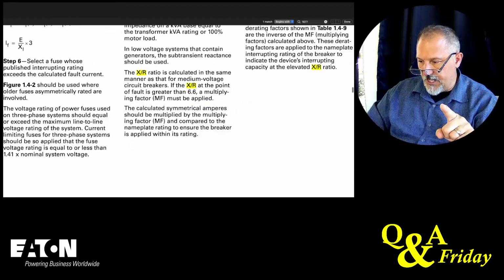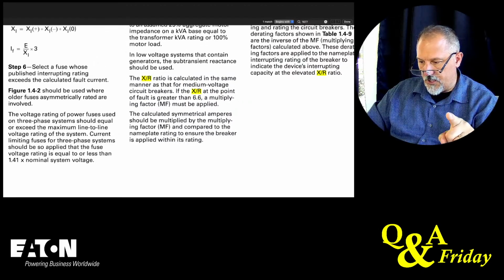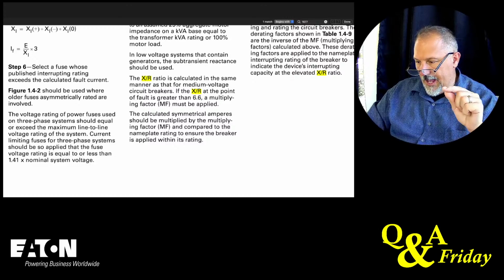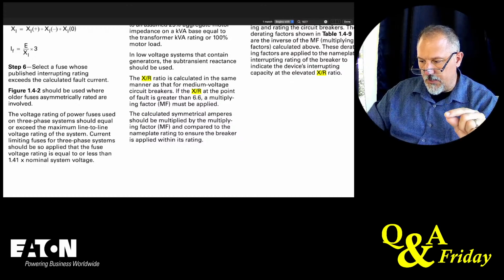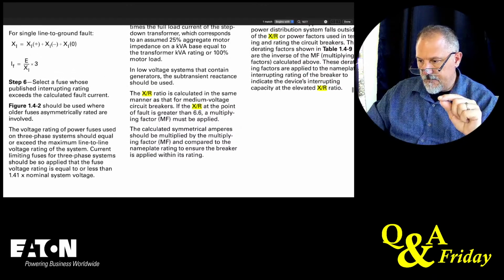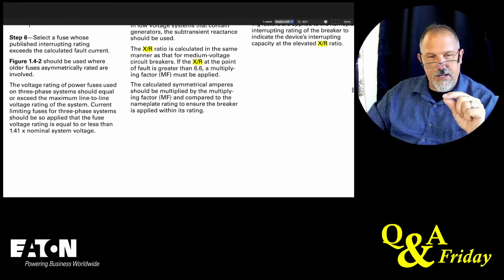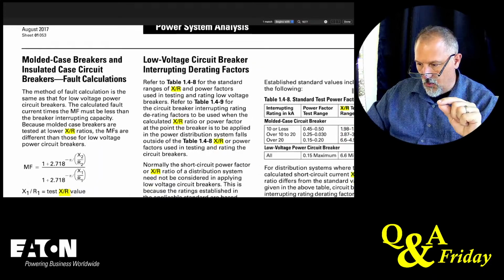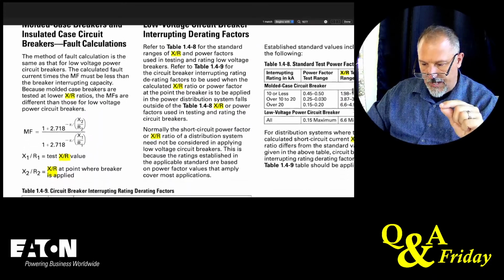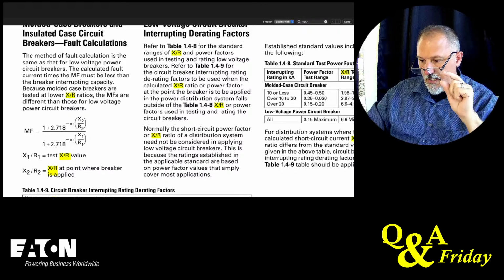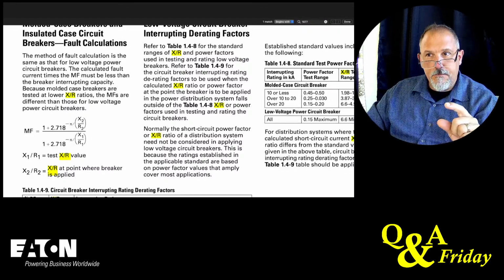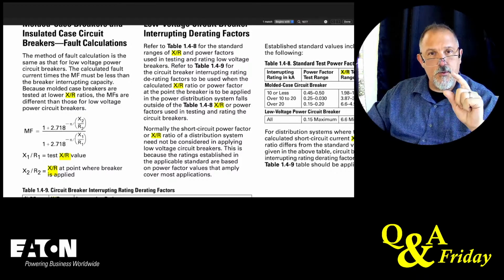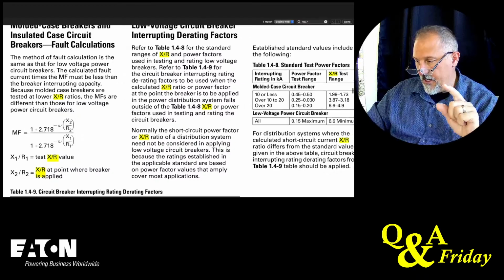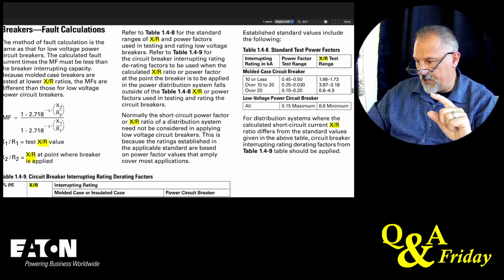Okay, the X to R ratio is calculated in the same manner as that for medium voltage circuit breakers. If the X to R at the point of fault is greater than 6.6, a multiplying factor must be applied. You've got to figure out what you're actually able to interrupt with that circuit breaker, because we test it with a 6.6. If it's greater than that, then you have more X, and you're going to have to adjust the interrupting rating of that breaker. And there's your testing range.